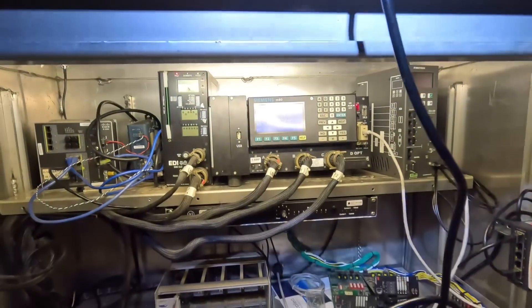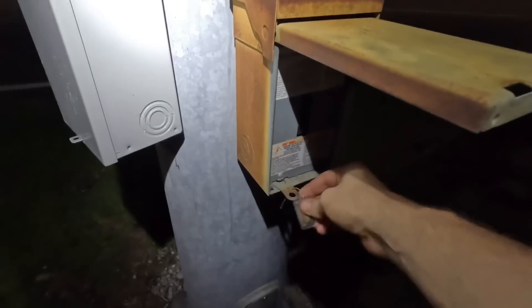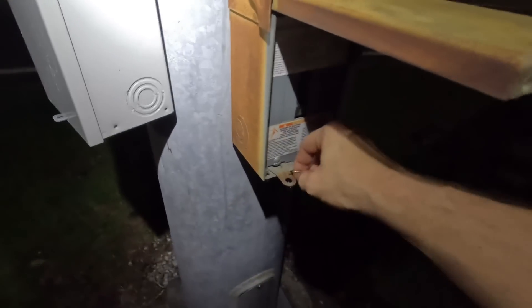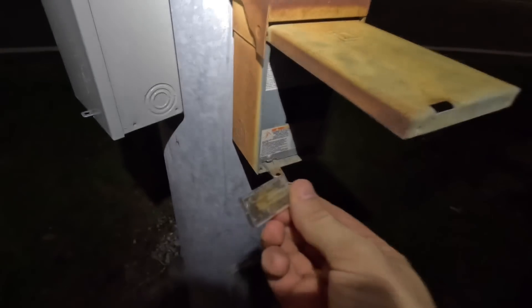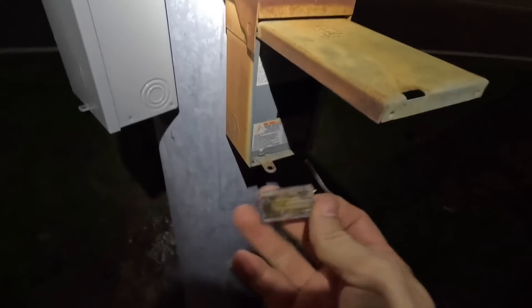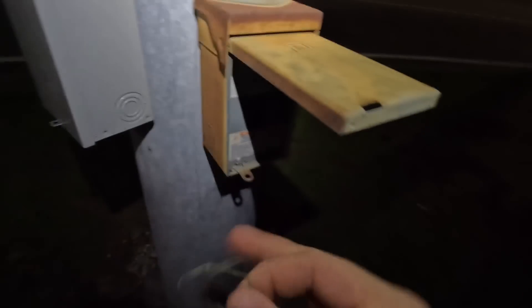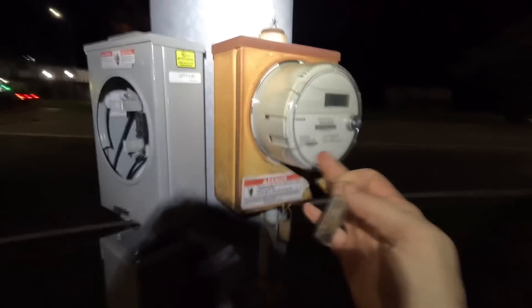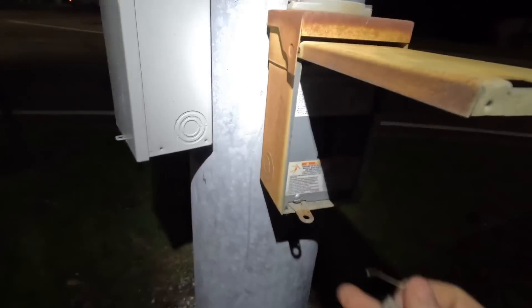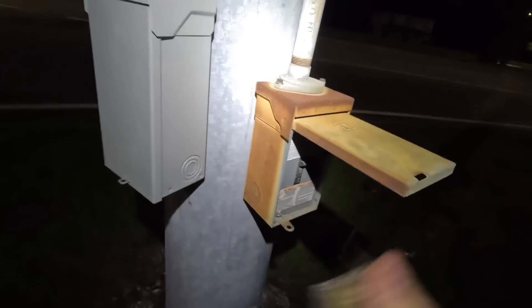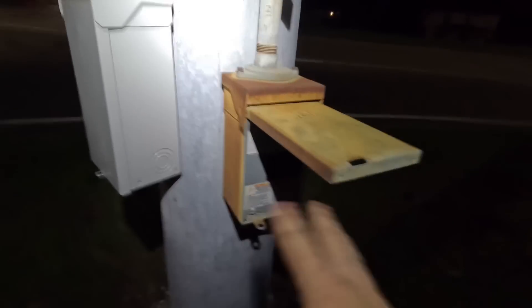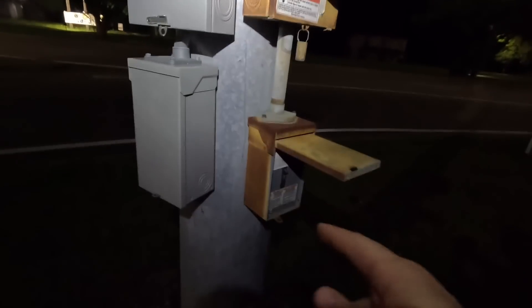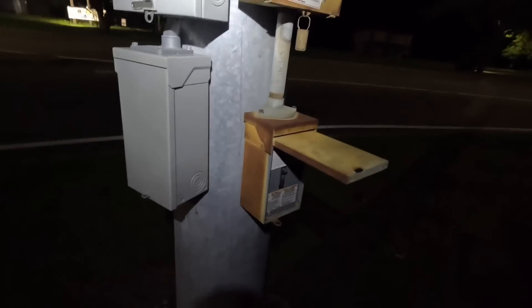So in a previous video I was showing off a tool and kind of stating how I cut these little steel lockout tagouts. For reference, that's like either emergency purposes. Say this meter is mounted onto a signal controller cabinet over here, I would need to cut this tag and be able to remove that meter. Or in this instance here, they had a tag on our breaker panel. It's getting cut and it's out of our way. Now we can actually use this breaker panel to kill power to the cabinet when we need to.